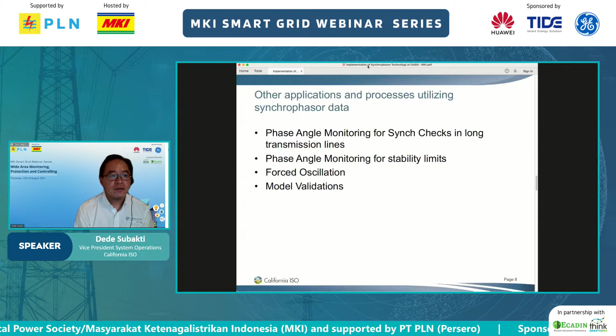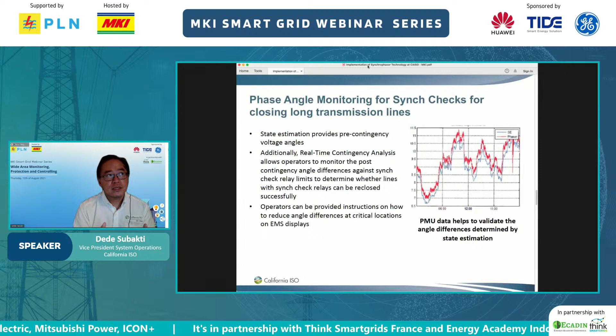Just like in Java, in California we have a lot of 500 kV long lines. It's very similar. On that 500 kV long line, if you have a contingency and the line trips, you have to close the line back in. But before you close it in, it has to be within your synchro phase, within your sync check. It's a very easy, simple application that the transmission operators are very used to.